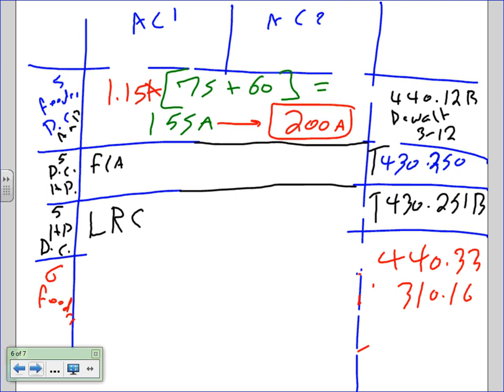Now remember, disconnect, guys, you have two sizes for it. There's an amp size and a horsepower size. The amp size, piece of cake. We've done it. Now the disconnect horsepower size. So this is number 5, amp size. Number 5, disconnect horsepower size. We do two calculations and we choose the largest. So let's do that. The full load amp of the first one is 75, plus the full load amp of the second one is 60. Add these up to 135 amps.